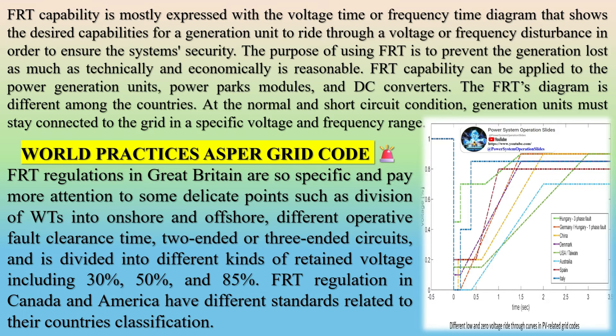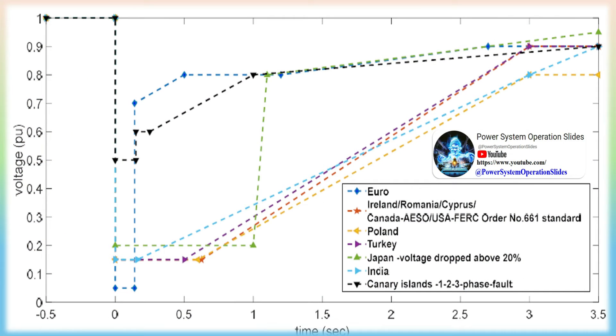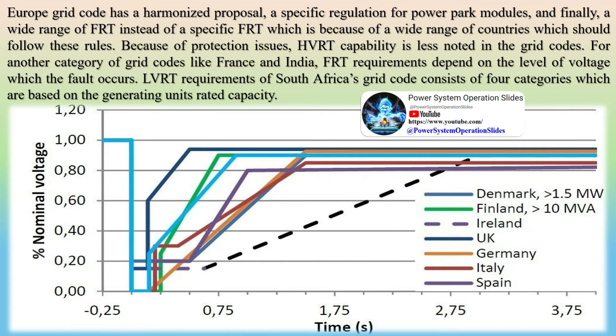FRT capabilities vary from equipment to equipment, and sometimes it takes a few seconds before the voltage returns to nominal level. In a PV system, FRT functionality allows it to continue operating even if the grid experiences a period of reduced voltage lasting one second or less. Specifically, when the FRT function operates, it is necessary to observe the voltage waveform for about five seconds after the drop to verify grid stability. A power quality analyzer capable of capturing the power situation before and after such an event is useful. FRT capability is mostly expressed with the voltage-time or frequency-time diagram that shows the desired capabilities for a generation unit to ride through a voltage or frequency disturbance.